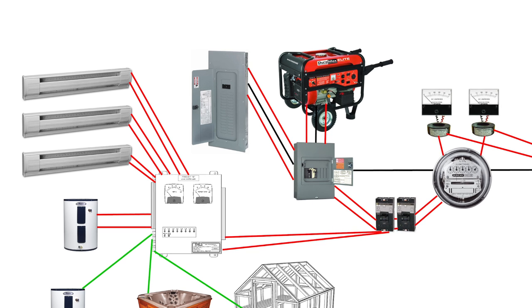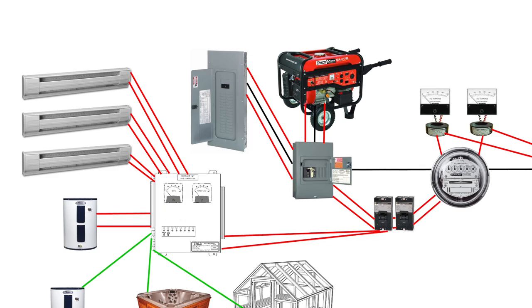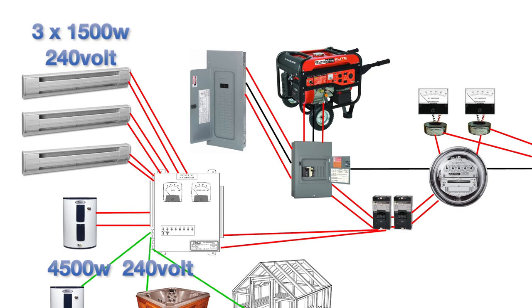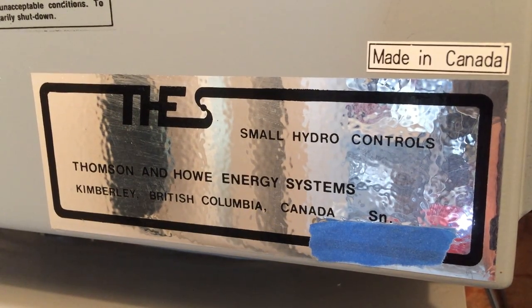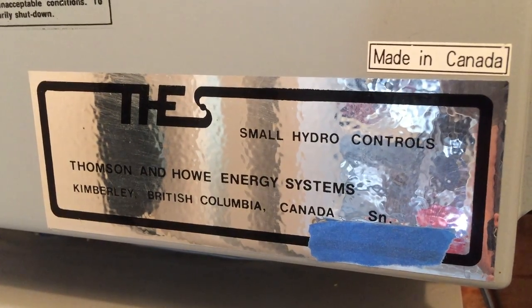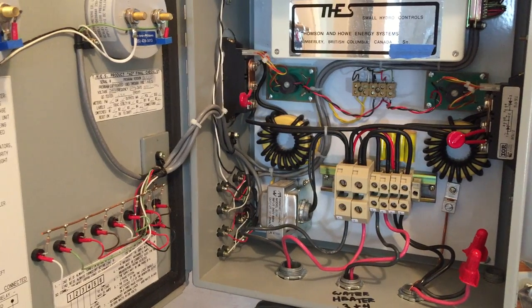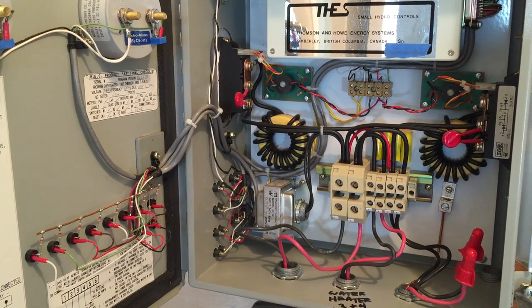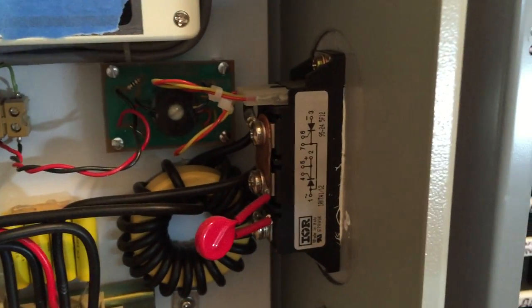Initially, we will run the system with the same load controller configuration that existed on the original spring fed system. The resistive loads currently are a 4500 watt water heater and three 1500 watt baseboard heaters for when the water heater has heated all of our domestic water. Our load controller was manufactured in Canada by Thomson and Howe and it has worked flawlessly for decades to automatically balance the load to the generated power. It does this by using a mini computer to monitor the speed, or hertz, of the system. If the hertz starts to rise, it means there is more power being generated than used, so a portion of the sine wave of the electricity will be shunted off to a resistive load by two thyristor switches in the load controller.